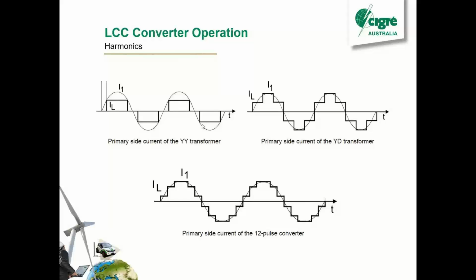It shows you what some of the currents look like in the transformer now. So this was just what we'd have with a 6-pulse with a YY connection. And then this is what the current looks like with a Y delta. If you've just had a 6-pulse, and then if you combine them together for the 12-pulse, this is what we get. So you can see it's still not great. It's definitely not a sine wave, but it's better than a 6-pulse, much better.